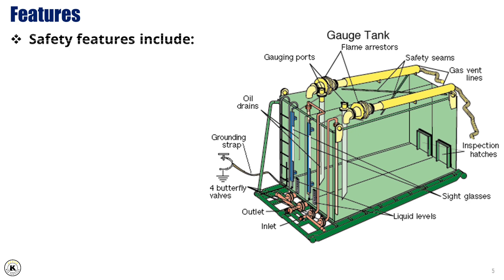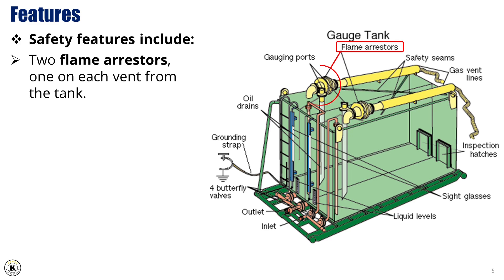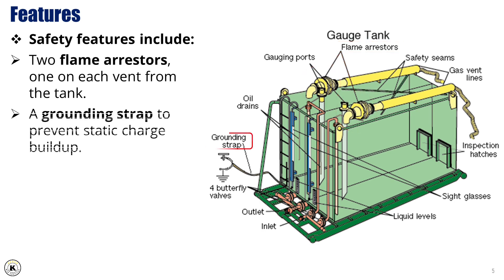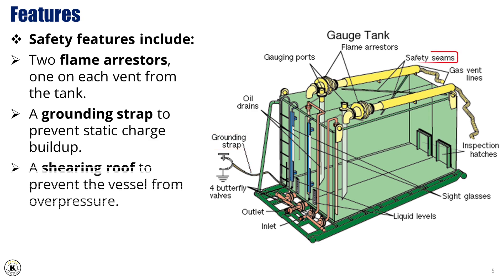Now let's take a look at the safety features of the atmospheric gauge tank. Each tank is equipped with two flame arresters, one installed on each vent, to prevent any external ignition sources from reaching the contents. A grounding strap is also in place to discharge static electricity, reducing the risk of sparks during operation. Lastly, the tank is designed with a shearing roof, which acts as a safety relief to prevent overpressure, helping to protect both the equipment and personnel on site.